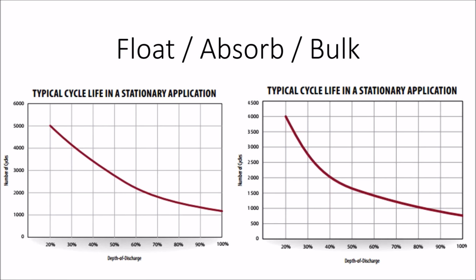And so temperature and the speed of the process matter. Solar is going to charge a battery in a period of about 4.5 to 5 hours, so it's going to charge at the 5-hour rate. An off-grid solar battery might be used for the opposite, 24 hours minus 5, so 19 hours. If you have a very controlled energy load at a constant level for those 19 hours, your battery is going to be discharging at the C20 rate. But if you have a tankless water heater and you run it for 1 hour, it might be discharging at a C1 rate, something much more quickly.